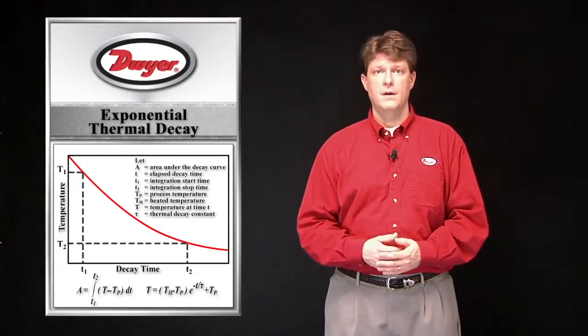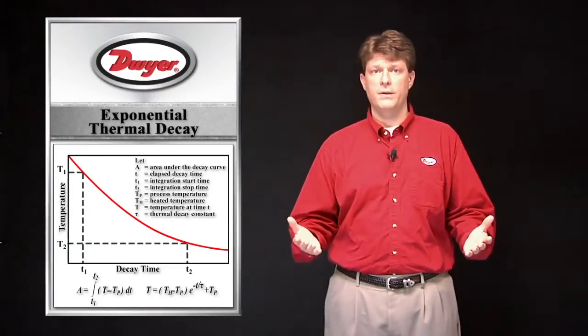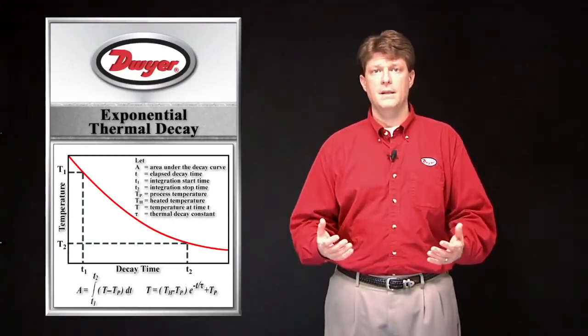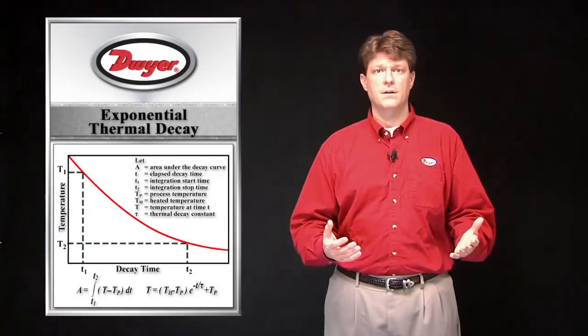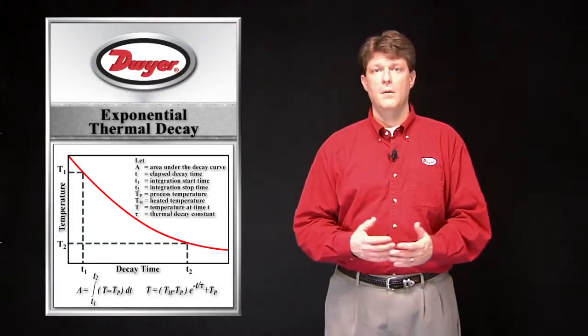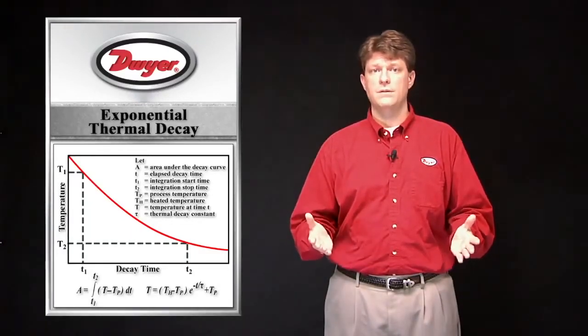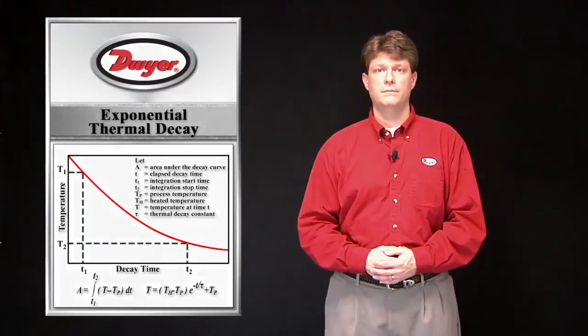the heated surface. There are several thermal dispersion techniques using either single or multiple temperature sensors. Commonly, RTDs are used as the sensor. RTDs are covered in detail in Tech & Spec number 13. Multiple temperature sensor models use a temperature difference between the two sensors to calculate the flow.